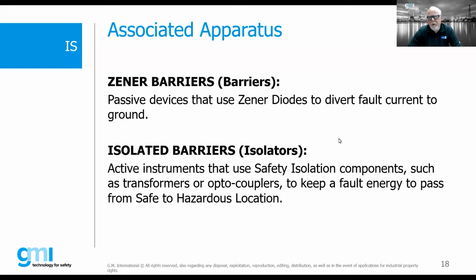They developed Zener barriers specifically for mine signaling applications, because they realized that just because we may be running 24-volt DC on our signaling, we could still generate enough energy to ignite the flammable methane gas found in coal mines. We had some major disasters in coal mines based upon signaling products generating too much energy. So those were the first barriers that were developed.